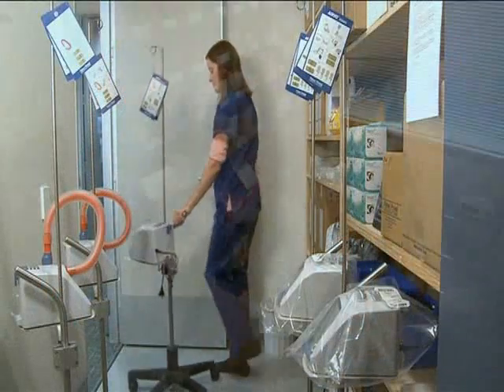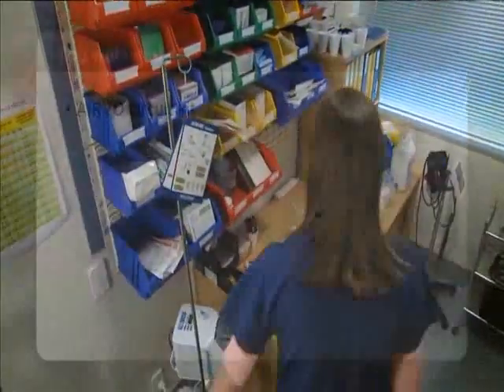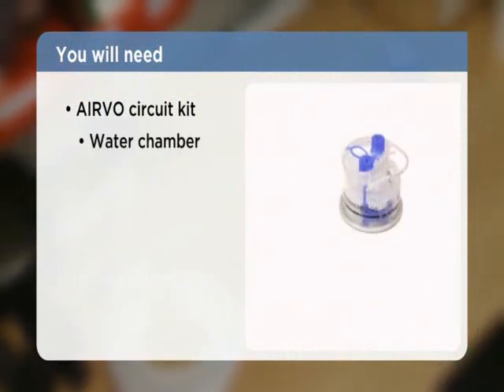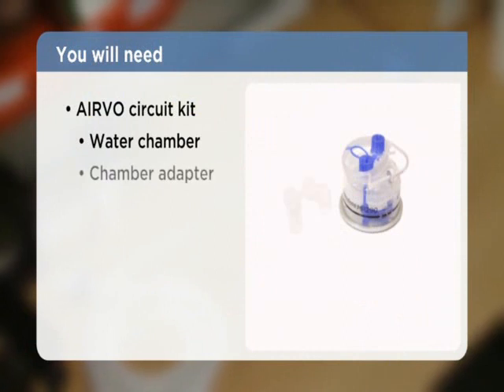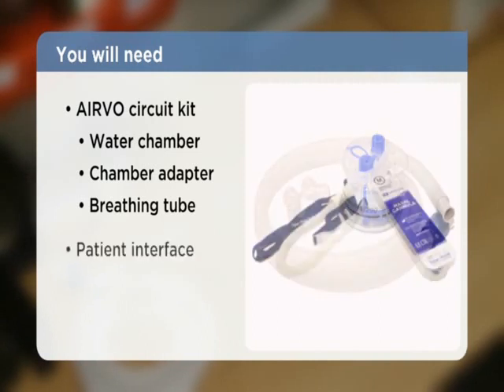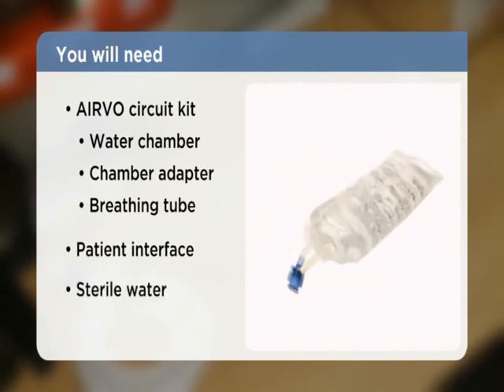Along with the AIRVO humidifier, we need the consumable accessories: an AIRVO circuit kit, which contains an auto-fill water chamber, a water chamber adapter, and a heated breathing tube; a patient interface from our range of nasal, tracheostomy, or mask interfaces; and a bag of sterile water. These consumables need to be replaced both for every new patient and at least every seven days.